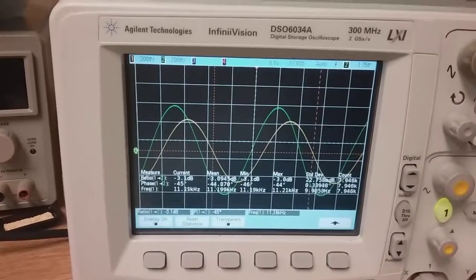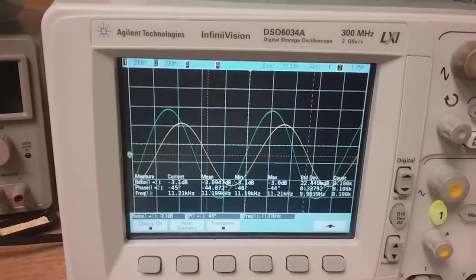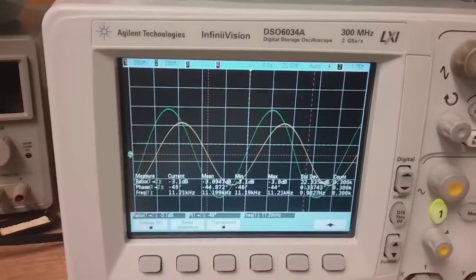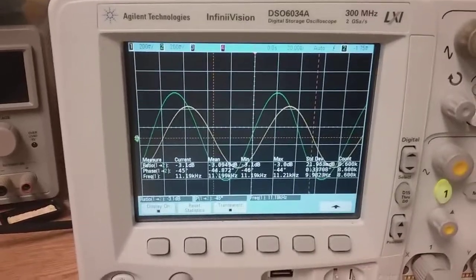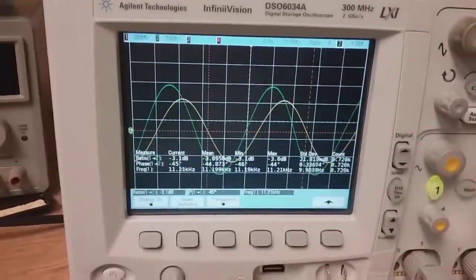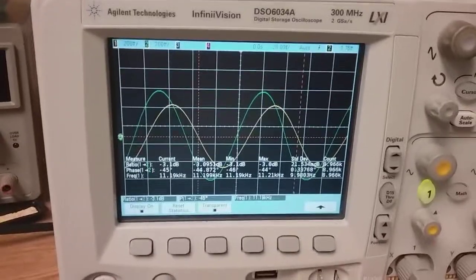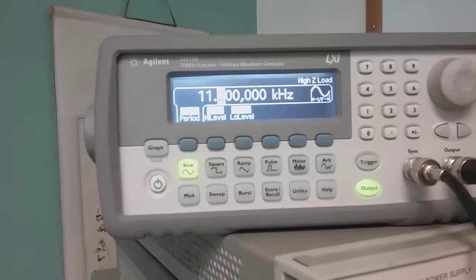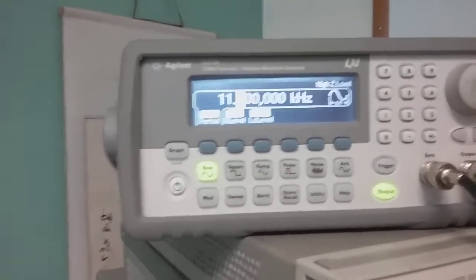This is as good as I can get it because it should really be about 3.01 dB, not 3, and 45 degrees, but this is pretty good. You don't have to exactly hit it, but it really does show if your measurement system is working.